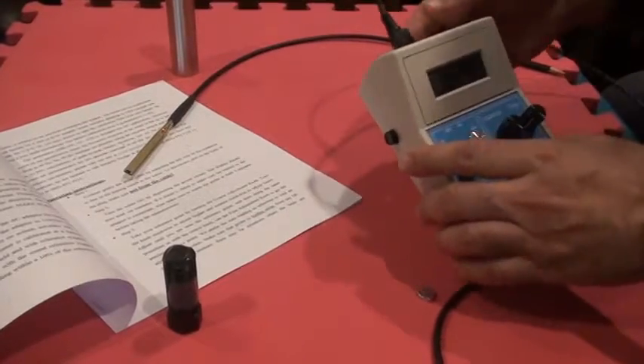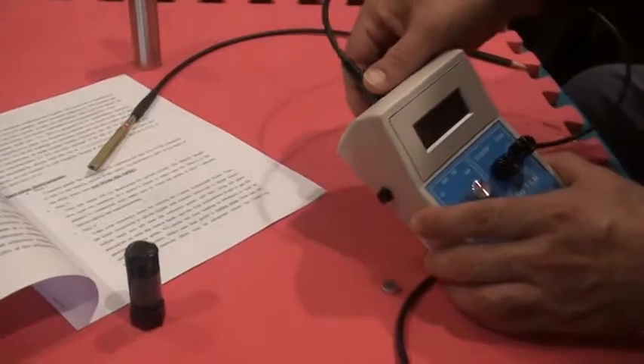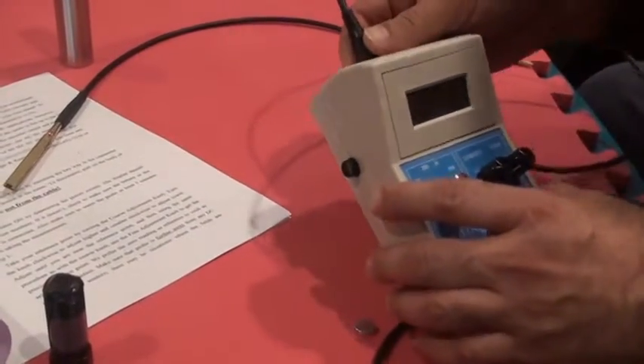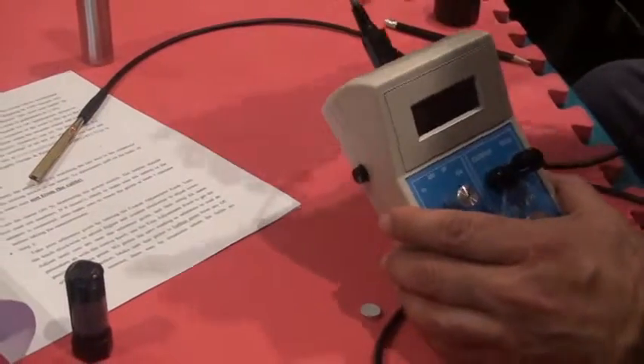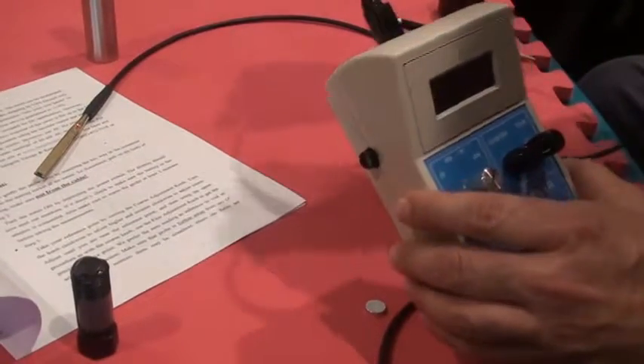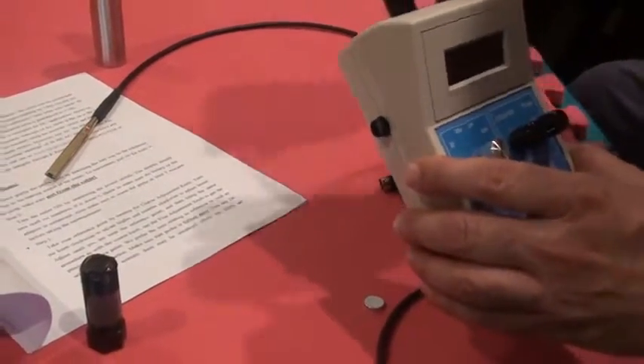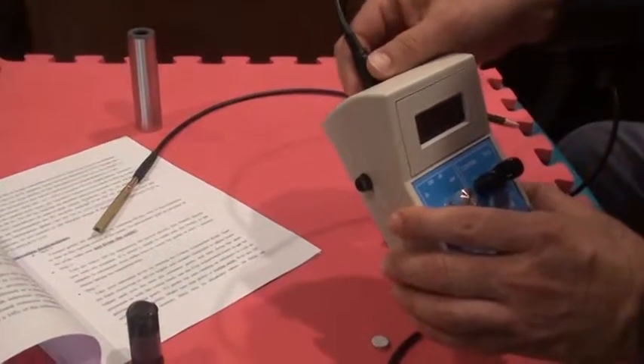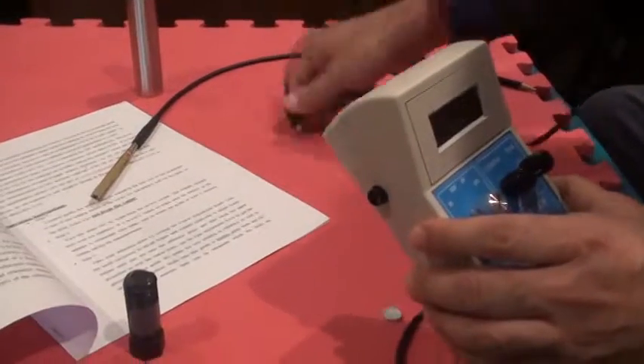This was a demonstration on how to use a transverse probe. Now I'd like to show you a brief description of how to use the axial probe. First, I have to unplug the transverse probe. Make sure when you unplug it, never pull it by the cable. There is a handle here, you press on it and you pull it out.